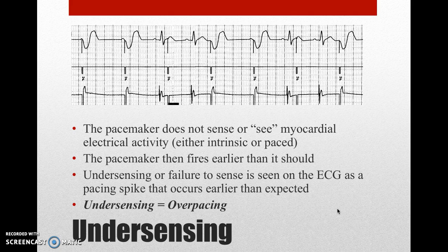Undersensing is a malfunction that occurs when the pacemaker does not sense or see myocardial electrical activity, whether it's intrinsic or paced. The pacemaker then fires earlier than it should. Undersensing, or failure to sense, is seen on the ECG as a pacing spike that occurs earlier than expected. Undersensing causes overpacing.